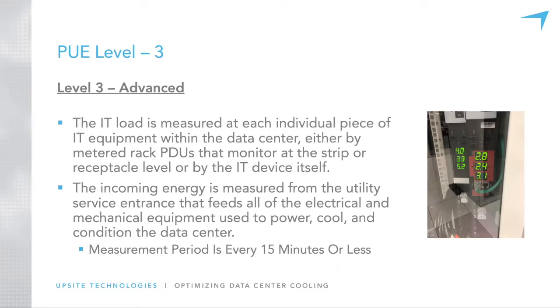And it's really important as we understand and can get a little more granular in how those outside variables affect our PUE. It goes back to if we're measuring this and we're understanding if it's 95 degrees in Ohio and humid, I know what my mechanical equipment is going to do. I know what, during my peak load, my CPU is going to do. And it allows me to make provisions to not only maintain my efficiency, but to make sure that I'm doing absolutely nothing to harm the reliability and health of the equipment and the facility itself.